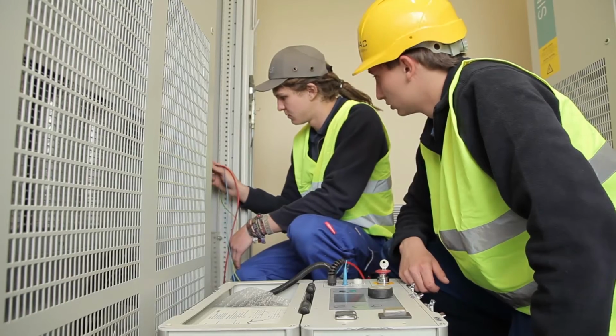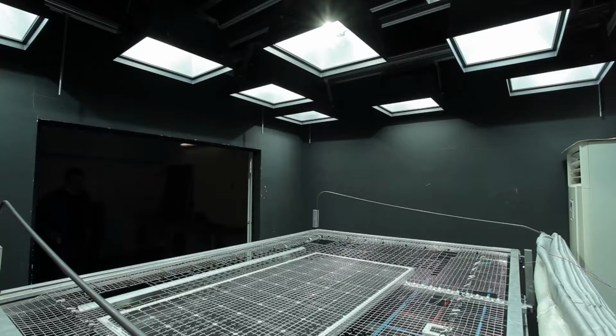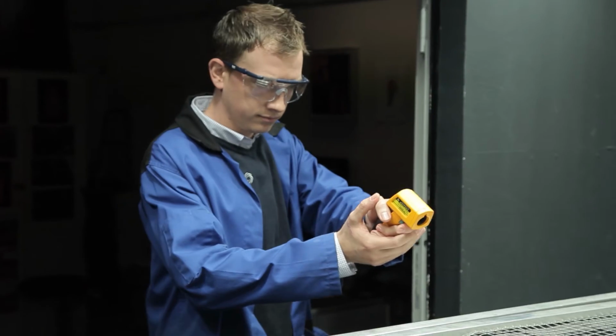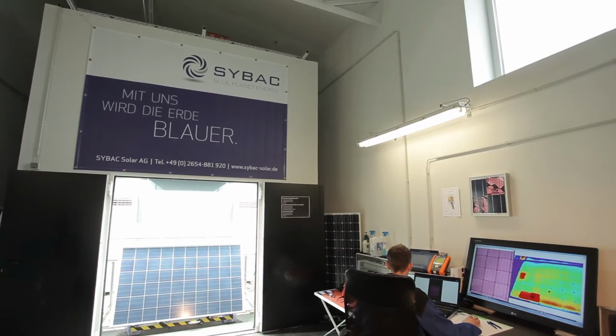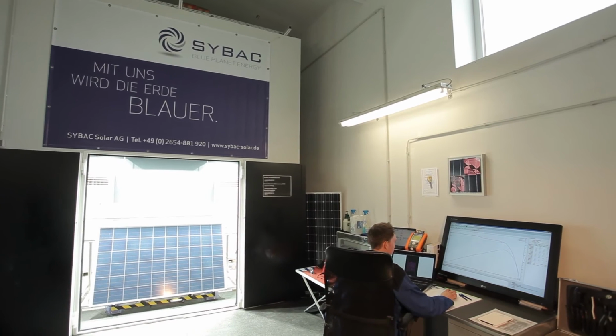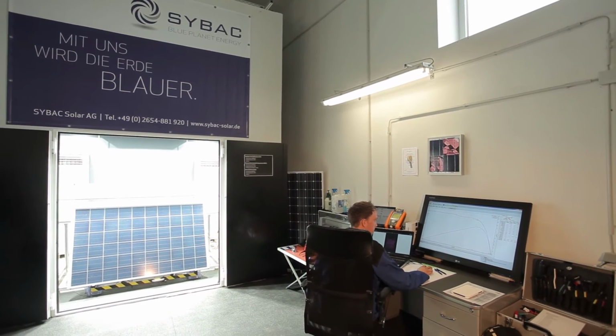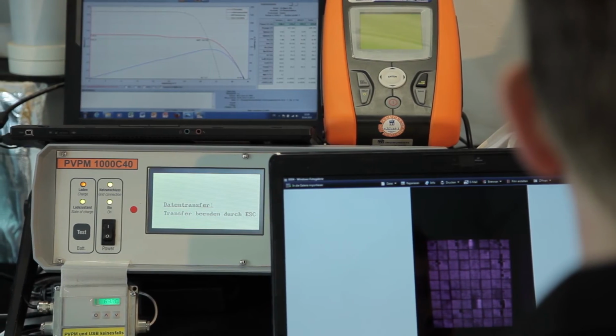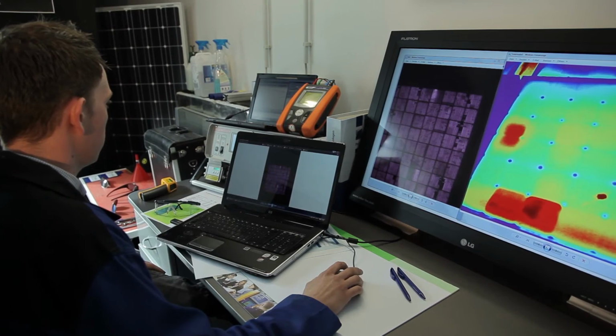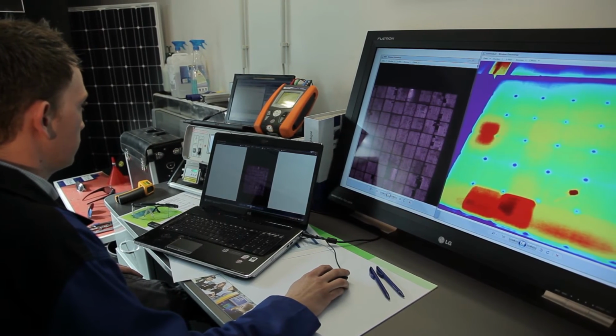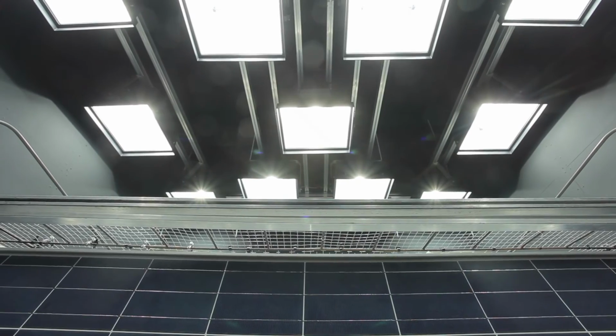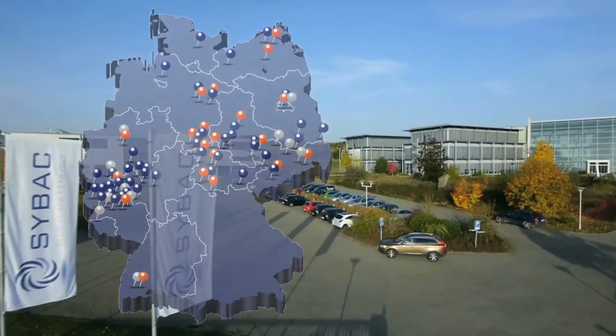Issues can be found by our specially trained service technicians on site or on the modules in our own laboratory. Extensive measurement technology and special equipment, such as a solar simulator, characteristic curve measurements, an electroluminescence chamber, thermal imaging, testing the insulating sleeve on high voltage cables, and earth measurements are used.